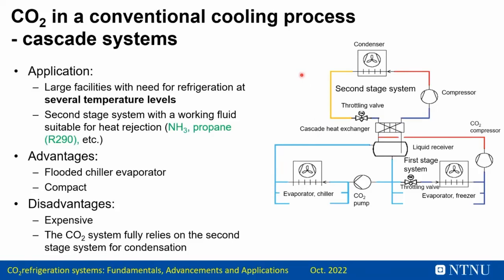When we look into a conventional cooling process, also a cascade system, in this case we have several temperature levels in the CO2 system, which is a benefit many times. And you see the same configuration on the left hand side, but now we have added a pump on this intermediate temperature level, and this pump is circulating CO2 at this level, maybe around -5 or -10, depending on where we want to have this temperature level. So we have flooded chillers in this part, and we have the evaporators, the freezers, on this part. Very compact and a robust system.